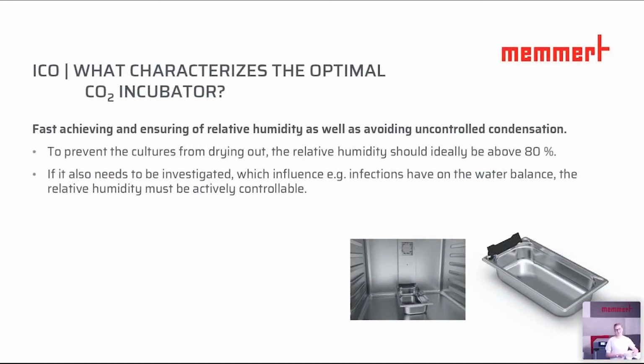Moving on to the second requirement, the humidity. Of course, we want fast achieving and assurance of the relative humidity inside, and we also want to prevent uncontrolled condensation, as I've said before. This is important to prevent the cultures from drying out, and ideally, the relative humidity inside should be above 80%. For most of our customers, however, it should even be above 90%. If it also needs to be investigated which influence sample-given infections have on the media inside, the relative humidity must also be controllable, but we're going to have a look at that later on in more detail. On the pictures down below, you can see our water trays, the bare water tray, and one picture is inside of an ICO chamber.